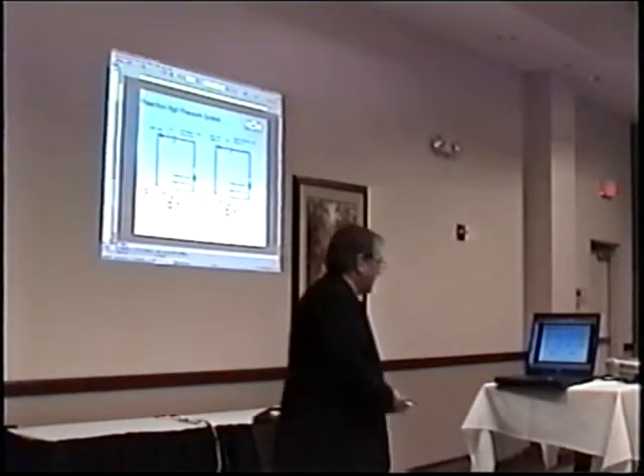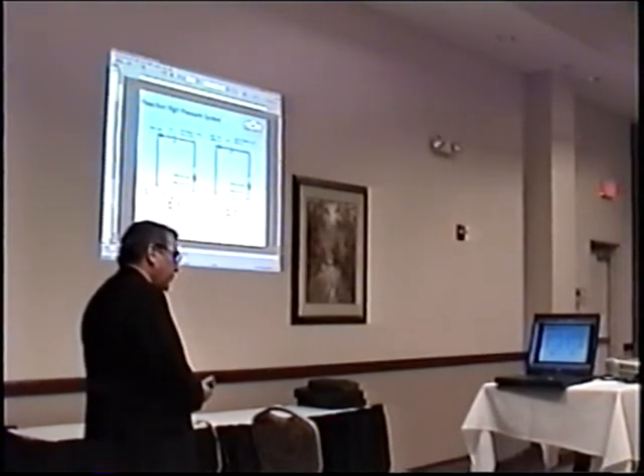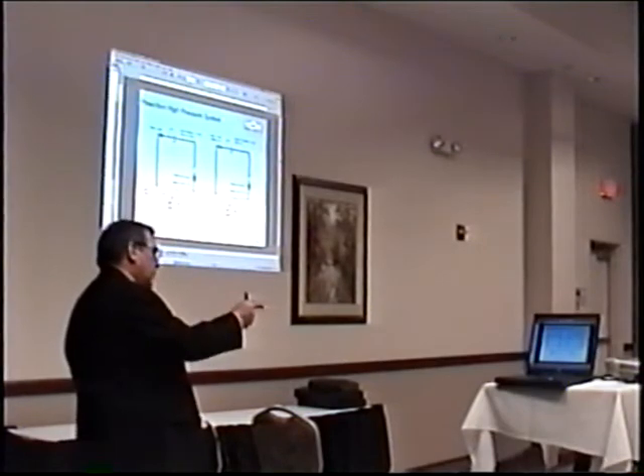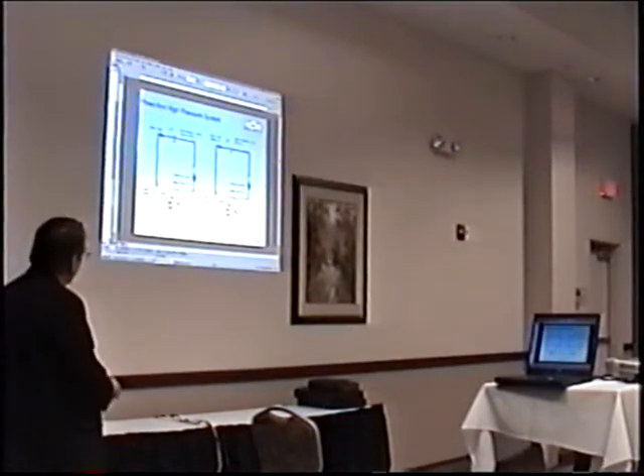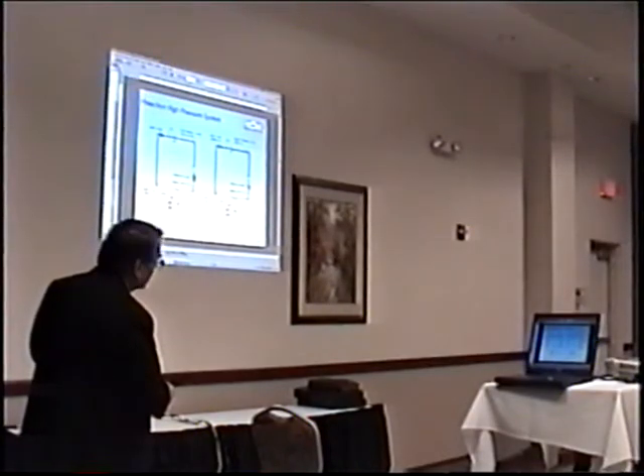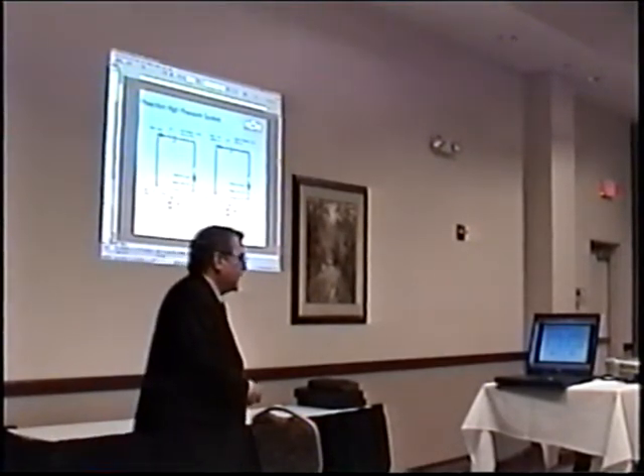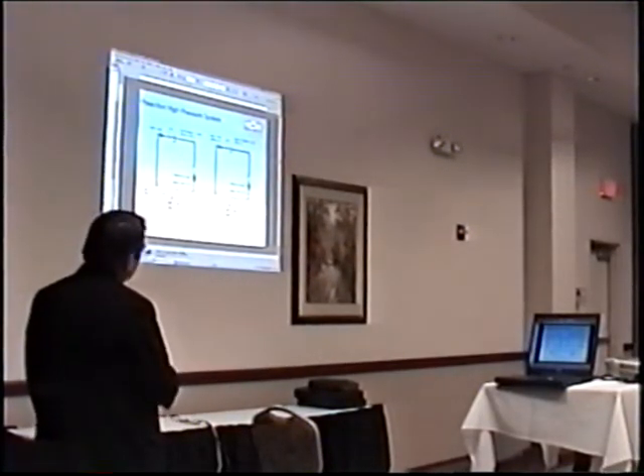So I designed an accumulator pre-fill that would fill the piping and bring it up to about 30 or 40 bar. What's supposed to happen is that the alarm panel says trip the system, it opens a valve on the unloader on the accumulator system, and that allows the accumulator to start to pressurize the common main. Then 2 seconds later, when this valve opens, the pressure's already there, and the accumulator fills the system. This pressure never drops below the start point for that pump. And the accumulator brings it up to about 30 or 40 bar, depending on the volume of the system.